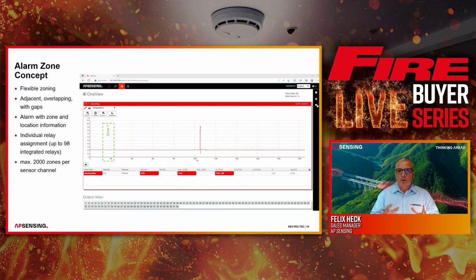In this slide, we see the temperature curve of a 2 kilometer long sensor cable, and the red one is the temperature curve. The sensor cable is 2 kilometers long, and it's not very practical to have one signal from a 2 kilometer long sensor. Please run the 2 kilometers to search for the fire. So we separate the sensor cable in zones. Here, for example, zone 1 can be directly connected to the second zone, and zone 2 has a different length in this case. We can have partially overlapped zones, for example, for escape routes in a tunnel also. There, the escape route is here in the middle, and zone 3 and 4 are partially overlapped.